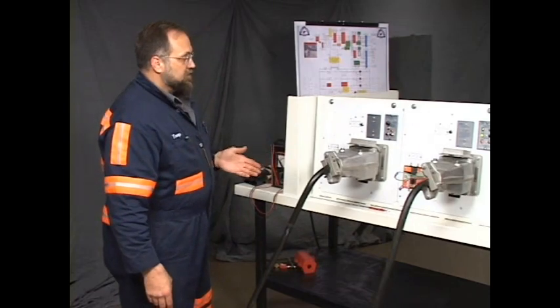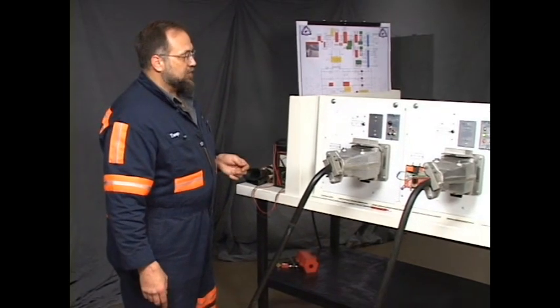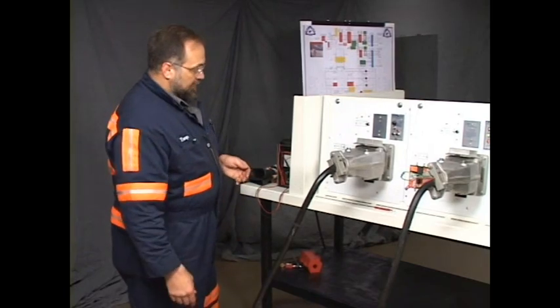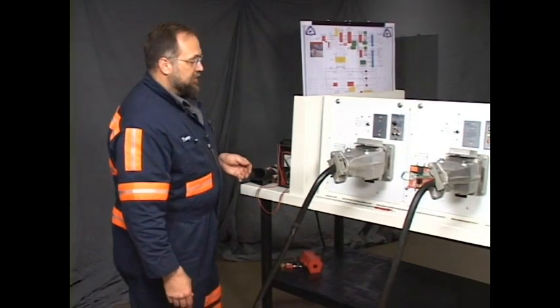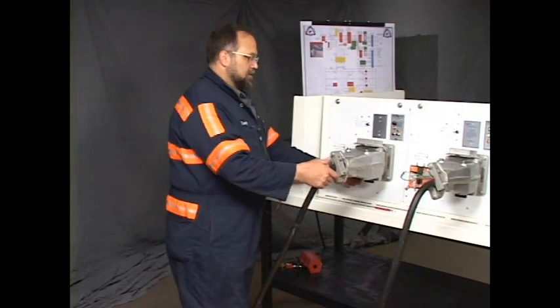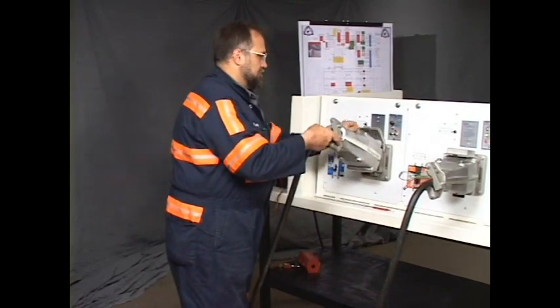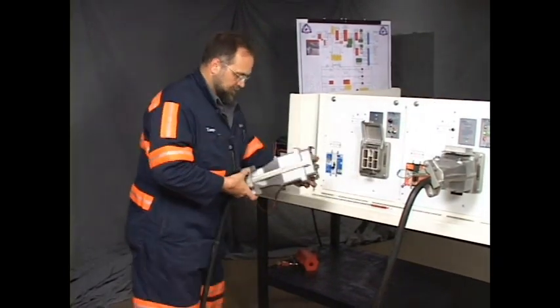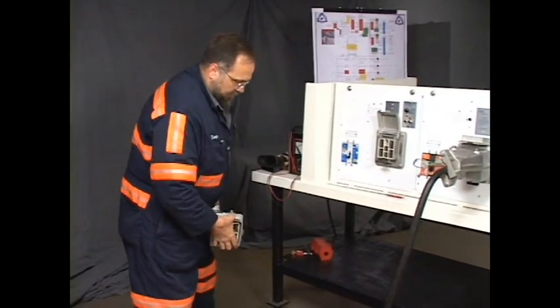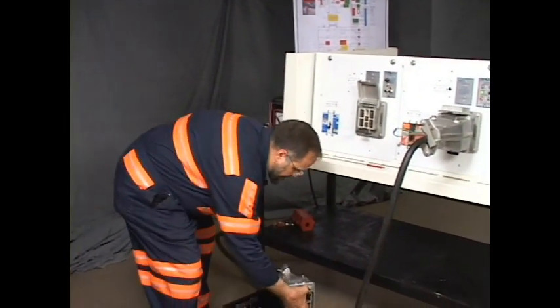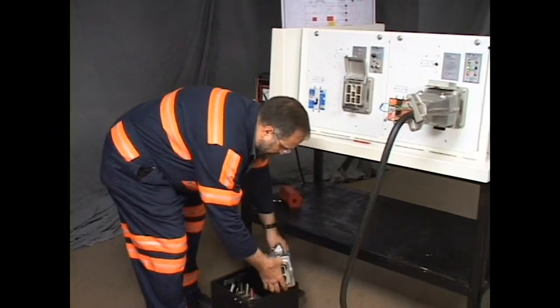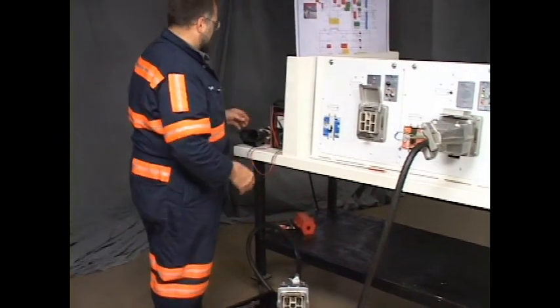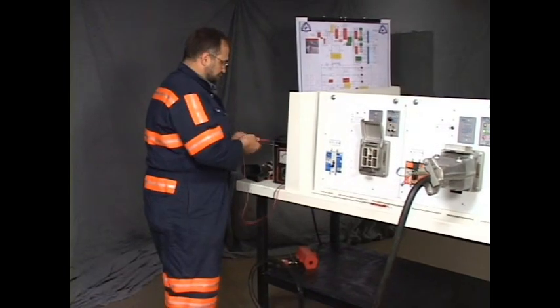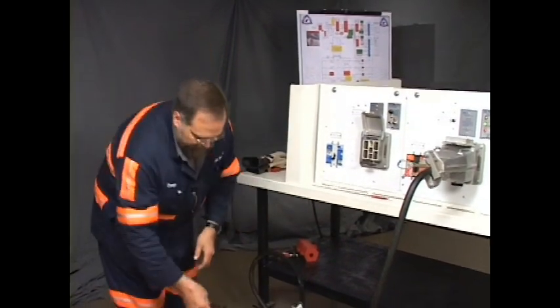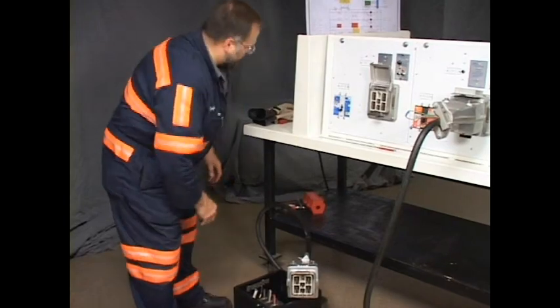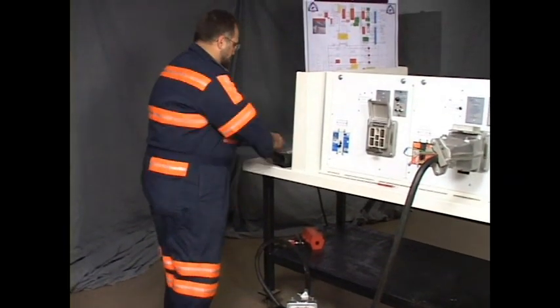You don't automatically assume that there's a problem with the ground monitor unit itself or with the power center itself. We're going to check the machine first. And to do that, I have to uncouple the cable coupler. I'm going to lay it right here where it'll be convenient to test. Take the instrument. Before we do any testing, we're going to lock and tag.